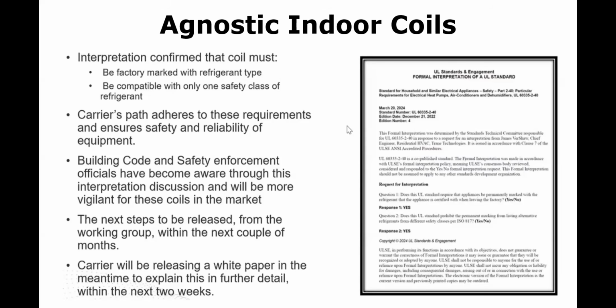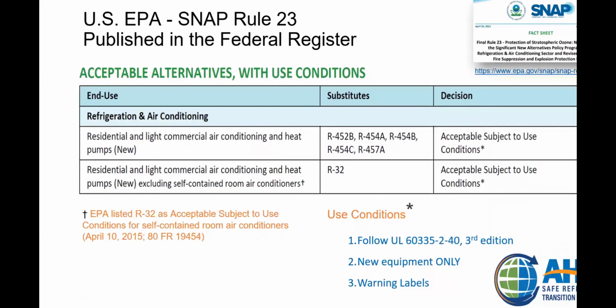However, there's like a lawsuit type thing happening with them to blockade them from doing that, with the main concern being people are just going to come in and say they want R22 or 410A, and they're really going to put it on R32 or R454B, and they're not going to buy the required safety controls that would normally come with an evaporator coil for those refrigerants and skirt the rules. That's the concern, and that's the reason why they're getting kind of blockaded. So I would not anticipate this going on. Well, it's a legal thing, so who knows how long it can go on. But my guess is that they'll probably get blockaded because they're the only ones doing it. All right, with that being said, let's move forward.